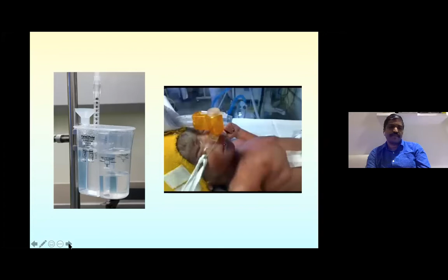To deliver CPAP, you need a compressed air source, compressed oxygen source, a blender, a flow meter, a humidifier, and a pressure generator. Could be a bubble or could be an interface like a flow driver. Now, what are the other requirements?